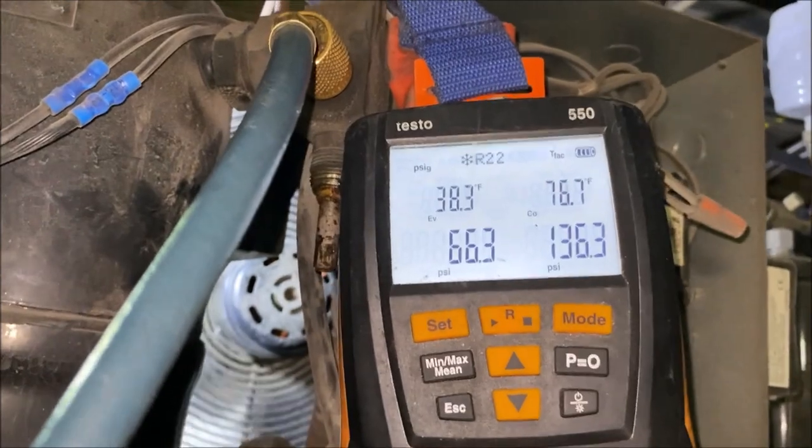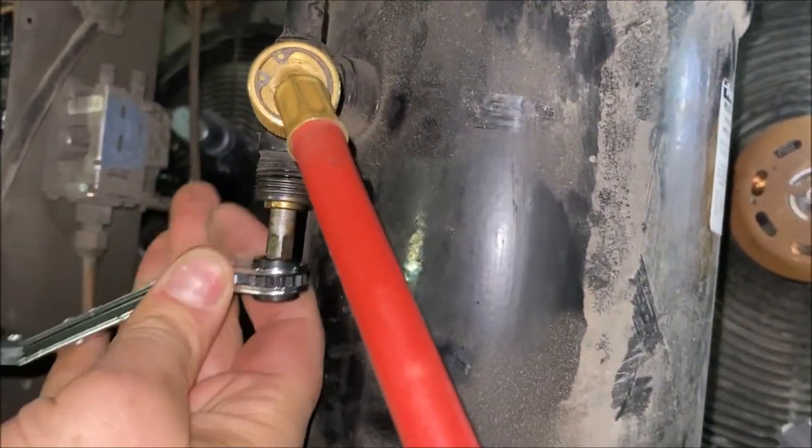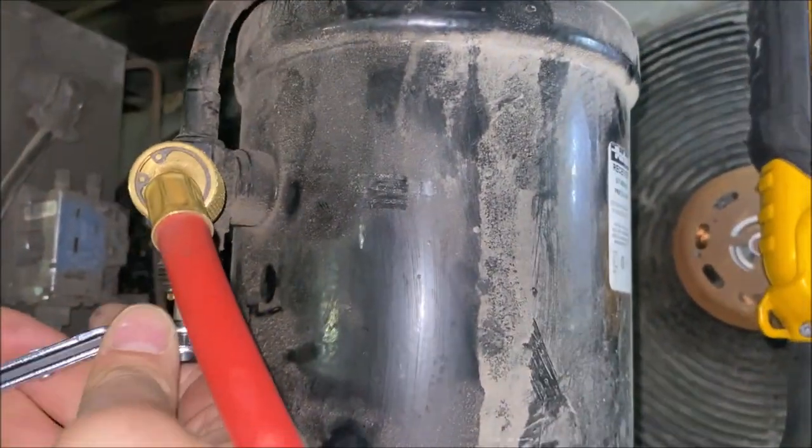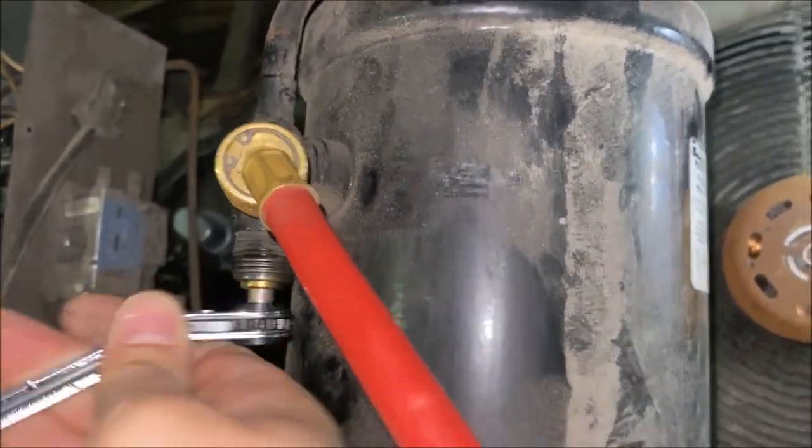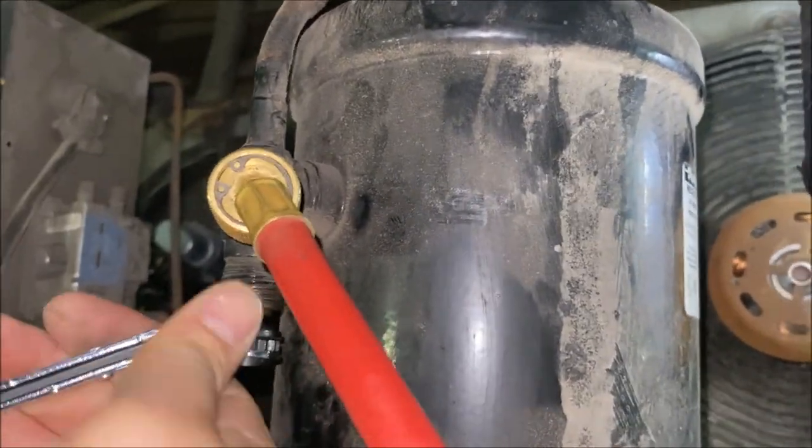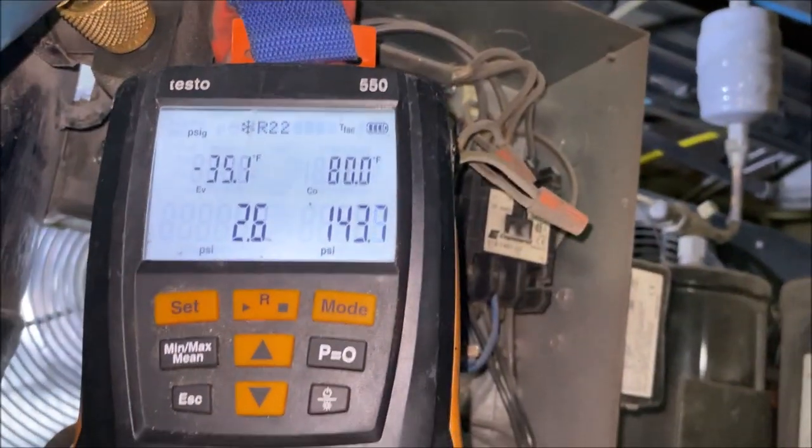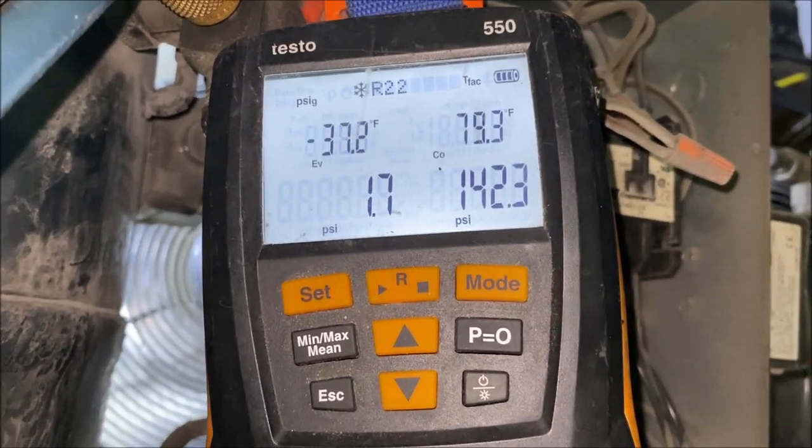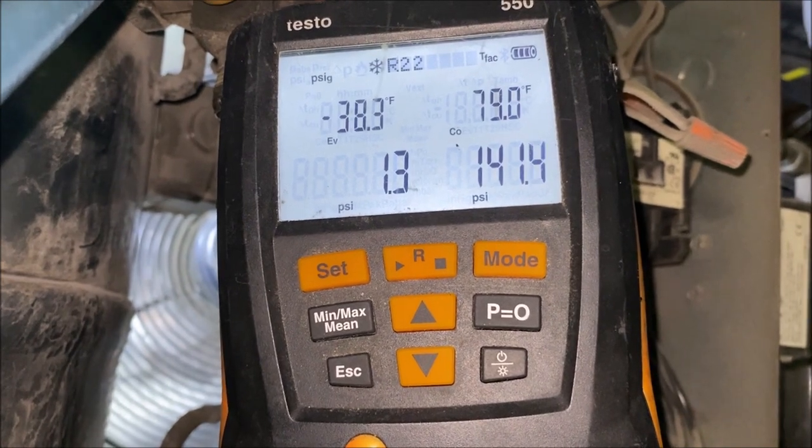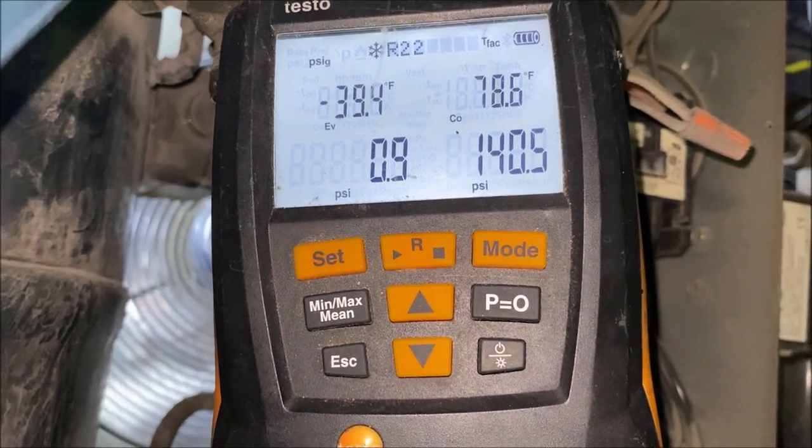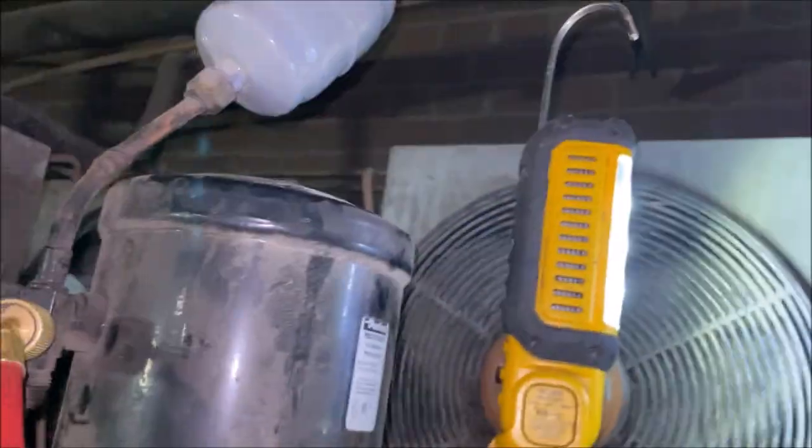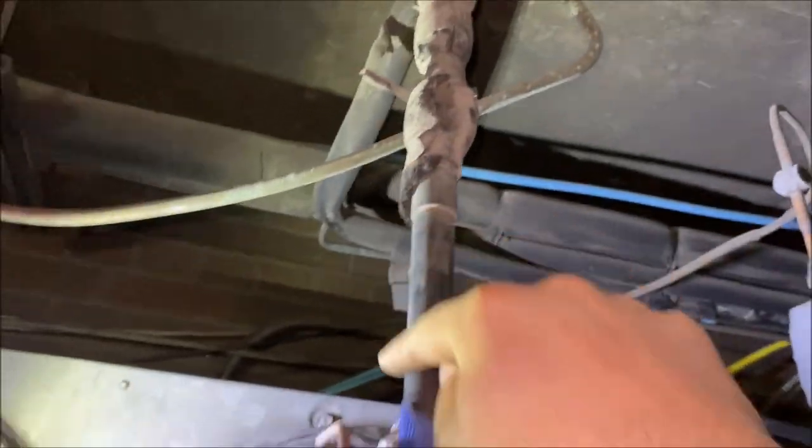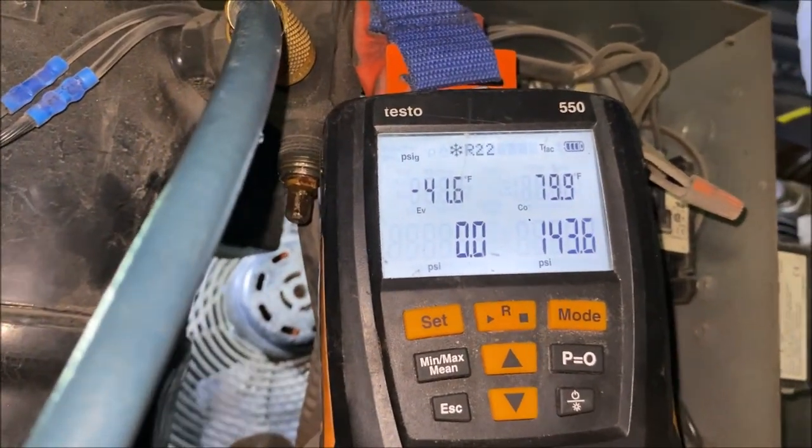So we're in pump down right now with the solenoid only. So we still have refrigerant just before the solenoid. So we're going to front seat this king valve very quickly here. Alright, so we're there. We're fully front seated. And now it's going to pump down the entire system. And we're only going to have refrigerant in our discharge and part of our liquid line up to the receiver. So we're going to pump it down to zero. Alright, so we're good here. We're going to turn off our system. And we're going to go right here to our suction valve and I front seated that as well, which parks all the refrigerant. So now we no longer have refrigerant in any of these lines going into the evaporator coil and back to the compressor. As you can see we have zero psi.